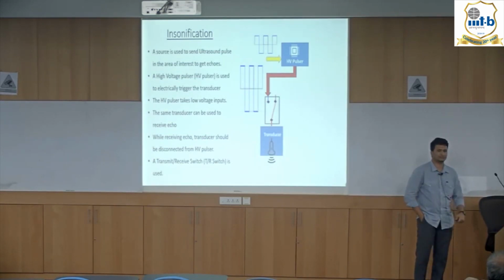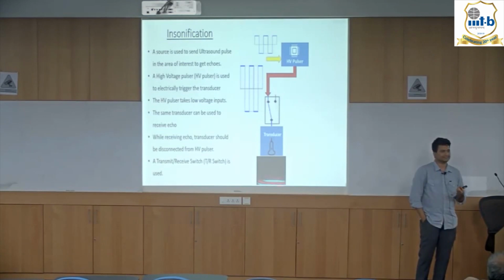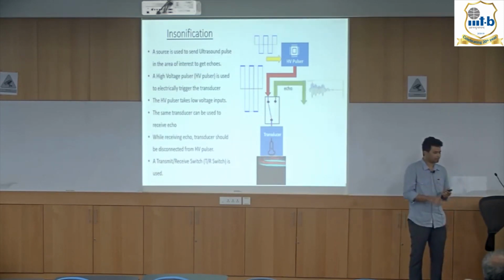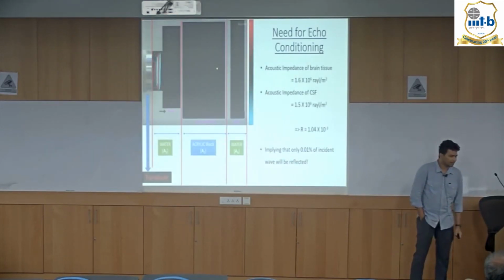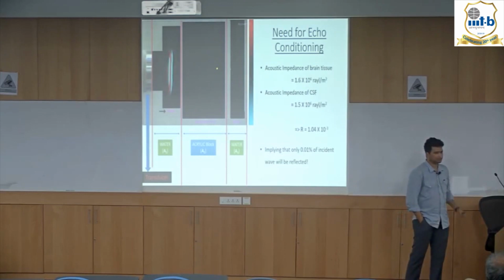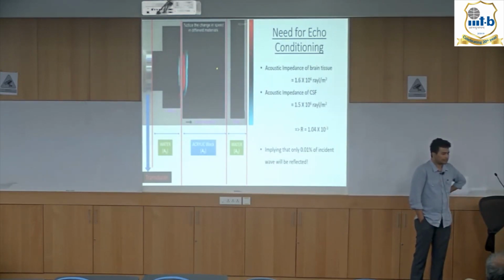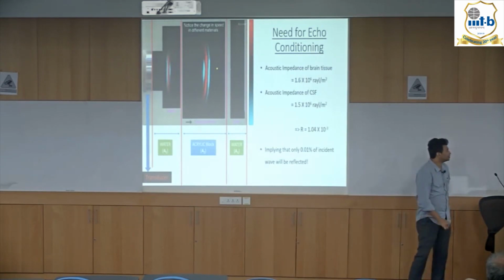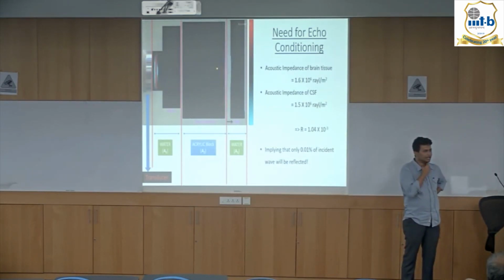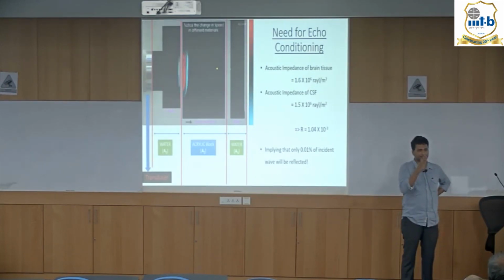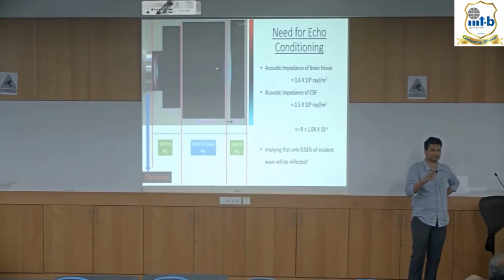We use only one transducer for both transmitting and receiving here, because it is extremely hard to make replicas of the same transducers having very close frequency responses or characteristics. So if we apply the previous equation that we had seen, the impedance of brain tissue is 1.6 megarayls, and that of CSF is 1.5. So the echo reflected from this interface between brain tissue and CSF is extremely low. It is just 0.01% of the transmitted pulse.